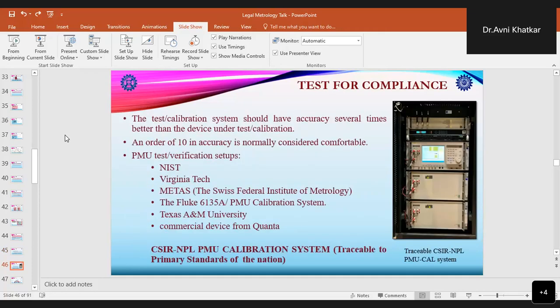Now for testing and calibrating any type of device, the test or calibration system should have an accuracy several times better than the device under calibration, and an order of 10 in accuracy is normally considered comfortable.